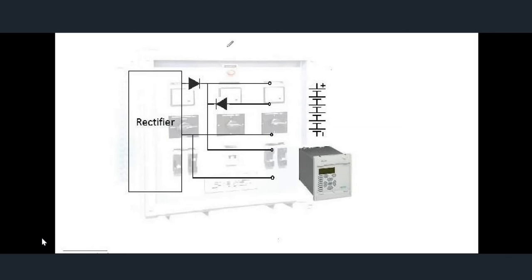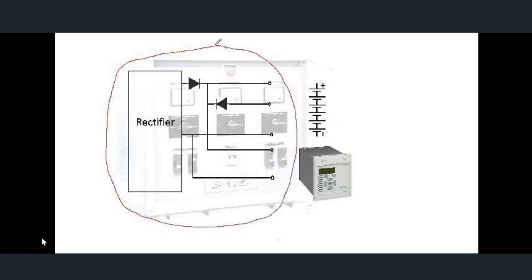What is inside a charger? If you consider this whole unit, it's a charger. Inside the charger there is a rectifier with a filter circuit. The input to the rectifier is AC and the output is DC — this is the positive terminal and this is the negative terminal of the rectifier. The battery and the load are both directly connected to the output of the charger. This output of the rectifier is directly connected to a diode in forward bias direction. This diode is used to block the flow of current from the battery towards the charger when there is no AC supply.